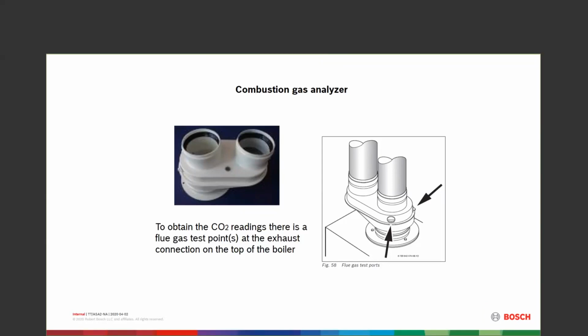And then the other thing to note on the vent adapter is that in the middle of the adapter, between the 2 pipes, there's another port there. That's so you can test your inlet air. So if you test your inlet air and find out you have carbon monoxide or CO2 readings on air and not 20.9 oxygen, you might have some cross-contamination going there. The other way that's easy to check for cross-contamination is to do your test with the cover off and then put the cover on. Once you put that cover on the boiler, everything should be the same. Nothing should change. No CO change, no CO2 change.